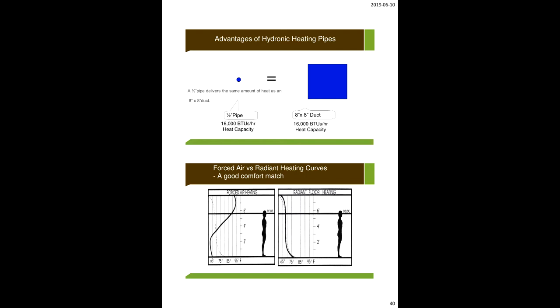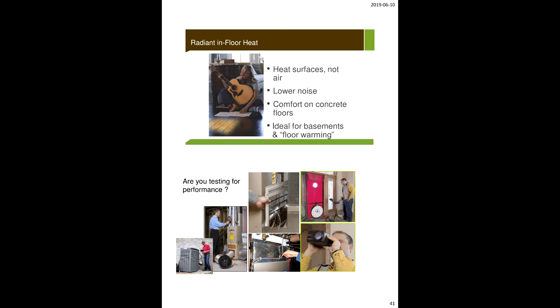Keep in mind, from the science perspective, 16,000 BTUs with a half-inch pipe with water versus 16,000 BTUs with a piece of ductwork—it's actually nice when you get homes with geometry that's odd, you can move the heat around a lot easier with a hydronic system. Naturally, it is radiant floor heat. It's a zone system, very comfortable. It addresses this mean radiant temperature issue very well.